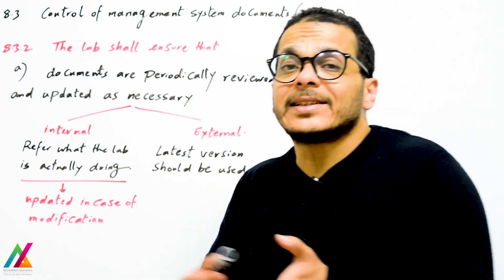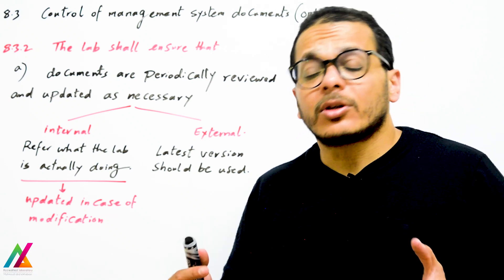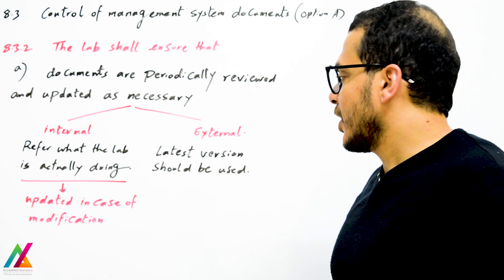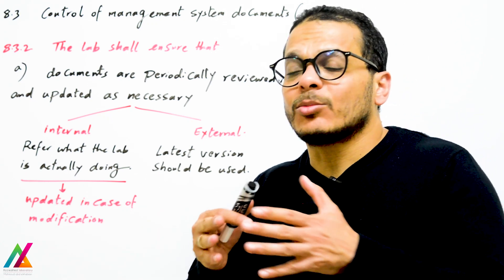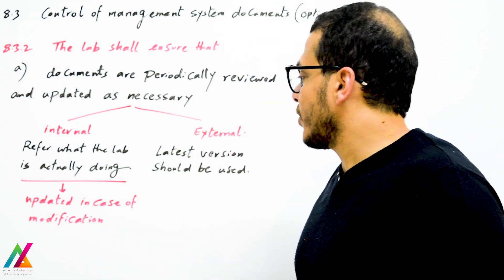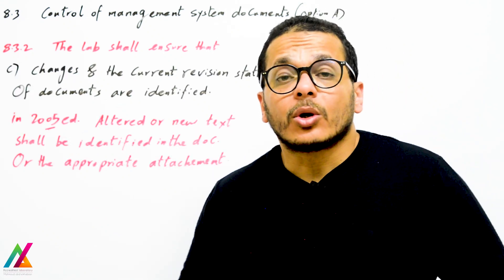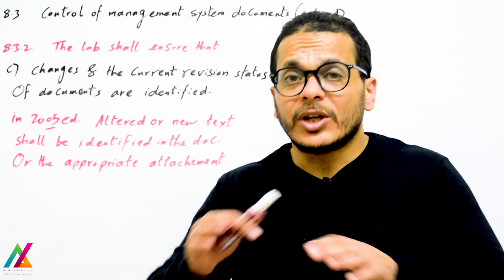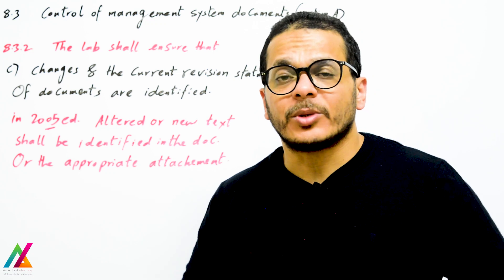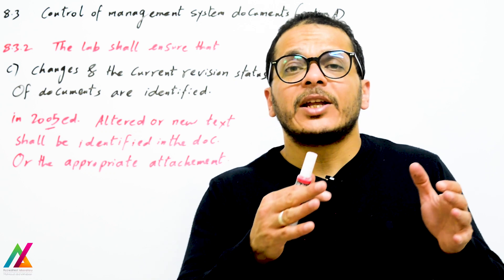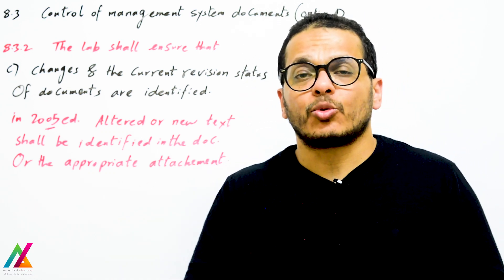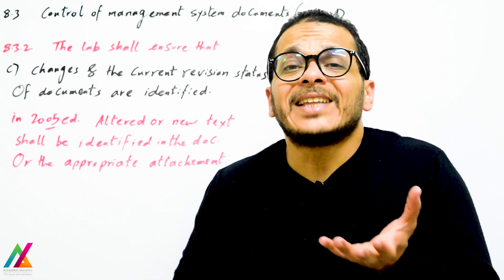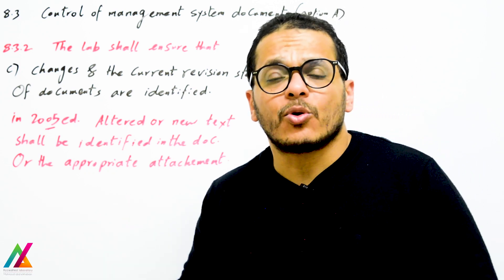The lab shall also ensure that documents are periodically reviewed and updated as necessary. For internal documents, if there is any modification they shall update the document and record the modification in detail. For external documents, the latest version should be used. All documents under the quality management system shall be revised within a specific schedule — for example, every three months reviewing a specific set — so that by the end of the year all documents have been revised.